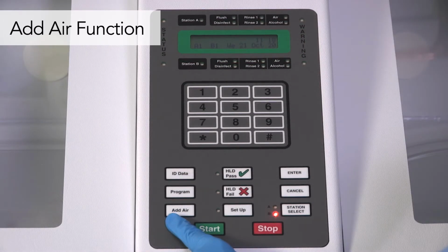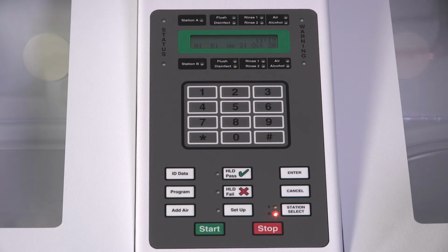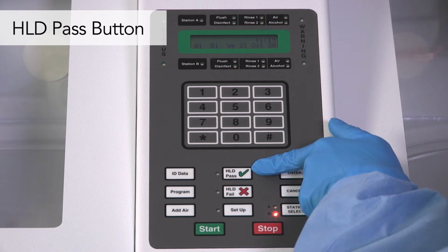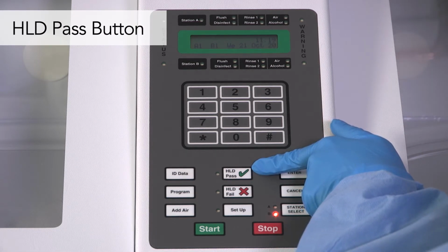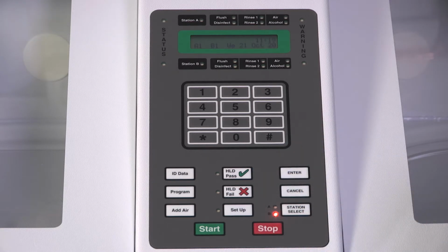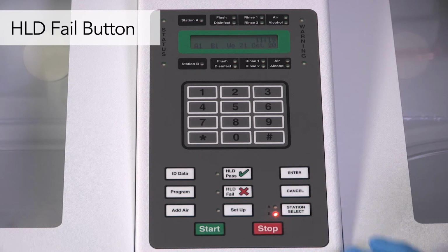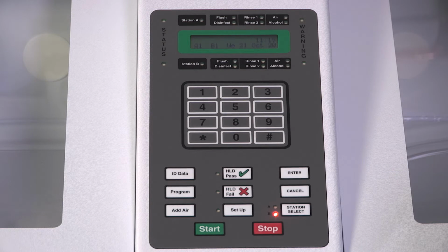The Add Air function is seldom used. However, when it is pressed during a disinfection cycle, an additional programmed amount of air is delivered. This function does not replace the endoscope drying requirement after high-level disinfection. Use the HLD pass button during the disinfection process after a test strip indicates the disinfectant met the MRC for the cycle. Use the HLD fail button during the disinfection process after a test strip indicates the disinfectant failed to meet the MRC for the cycle. The endoscope cannot be used in a patient procedure and must be reprocessed.